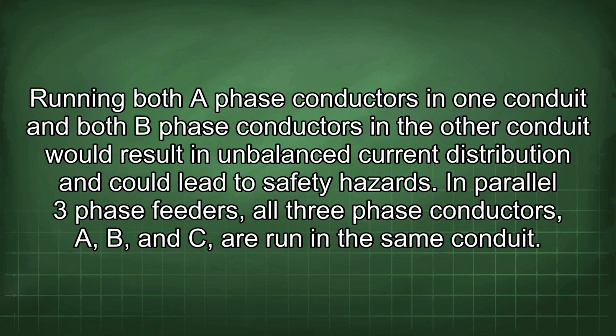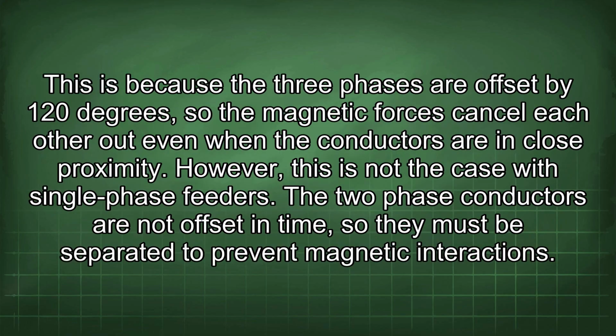In parallel three-phase feeders, all three-phase conductors A, B, and C are run in the same conduit. This is because the three phases are offset by 120 degrees, so the magnetic forces cancel each other out even when the conductors are in close proximity. However, this is not the case with single-phase feeders. The two-phase conductors are not offset in time, so they must be separated to prevent magnetic interactions.